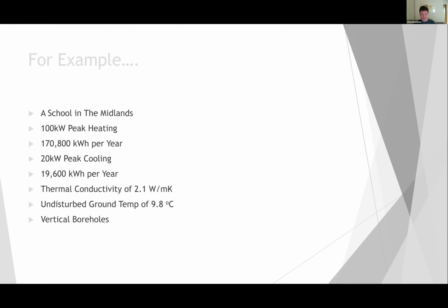I've used a thermal conductivity of 2.1, low to middle of the road for the UK, and an undisturbed ground temperature of 9.8. And as I said earlier, I'm going to concentrate on vertical boreholes. So if we look, first of all, at omitting the cooling entirely from the system, then we're looking at 2,508 meters of borehole in whatever configuration. We discussed that a few weeks ago, how important designing to a specific configuration is and sticking to that. So if you haven't seen that webinar, it's worth going back and having a look at it.